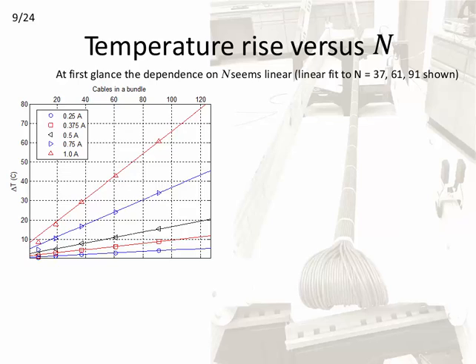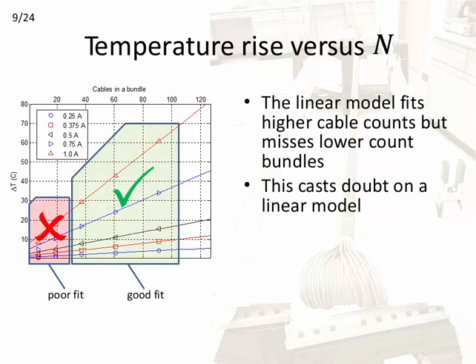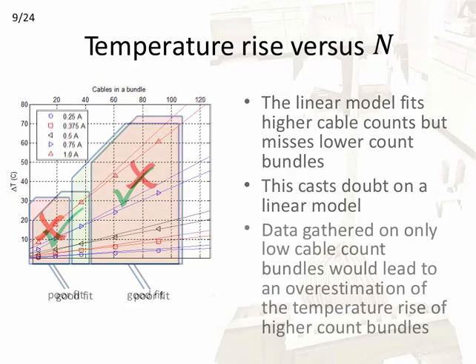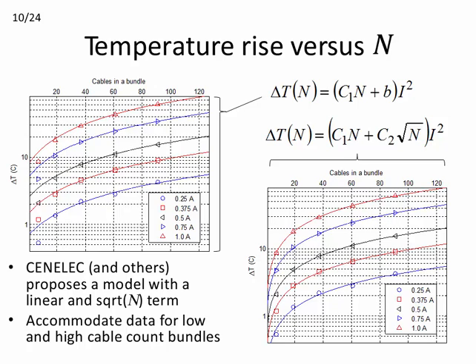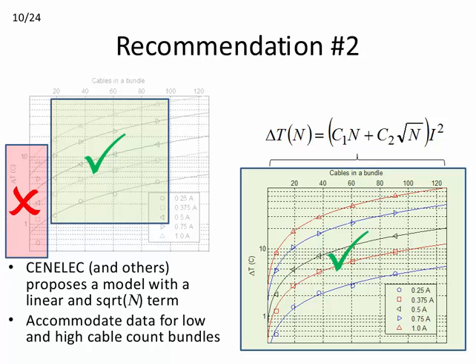We can also consider the temperature rise versus the number of cables in the bundle. At first glance, we might be tempted to use a straight-line fit to estimate the relationship between temperature rise and the number of cables. The closer inspection reveals that the linear model is a good fit to high-cable count bundles, but misses the data when the number of cables in a bundle are small. If one were to gather temperature rise on bundles constructed using only a few cables, extrapolation using the linear model would overestimate the temperature rise of high-cable count bundles. The linear model breakdown is more clear when we plot the same data on a log-linear plot. It shows that a better fit is realized using a linear and square root of n-term function to describe the relationship between the temperature rise and the number of cables in a bundle. This is a widely accepted relationship used by CENELEC and TIA and accommodates the temperature rise for high and low cable count bundles.